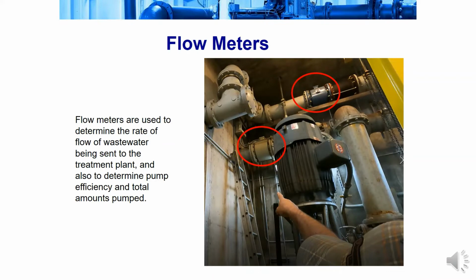There are also 2 flow meters in the pump room area that are used to determine the flow of wastewater being sent to the treatment plant. This is used to help ensure the pumps are running efficiently, as well as understanding the amount of hours those pumps have run and worked. One important note about these flow meters is that they are magnetic flow meters, so there are no moving parts that can be obstructed by wastewater, as you would find with an impeller flow meter or any other kind of flow meter.